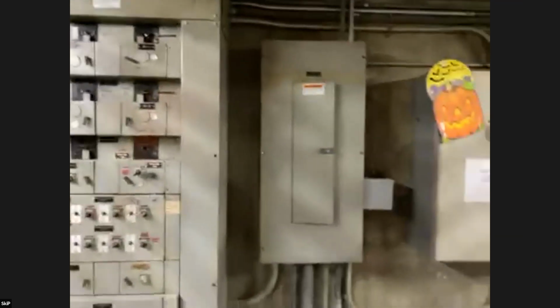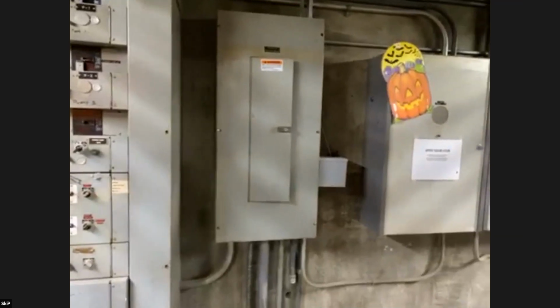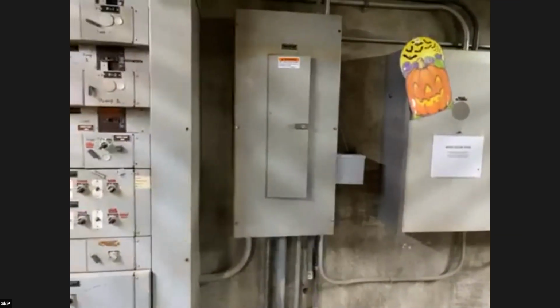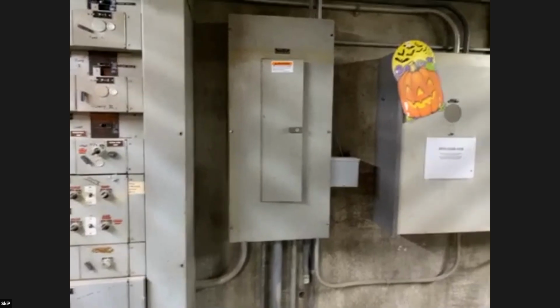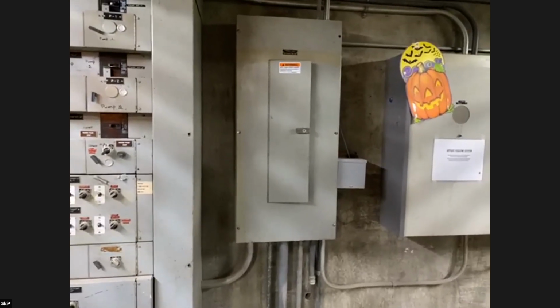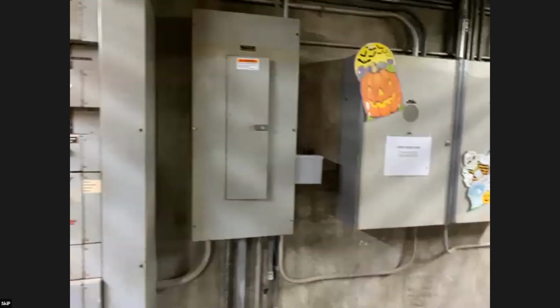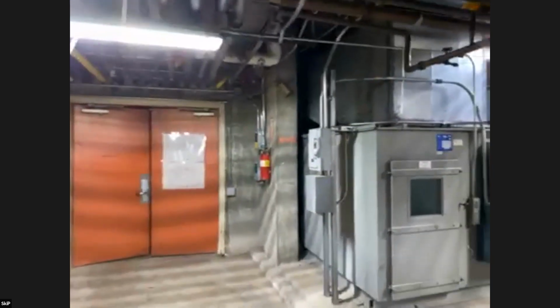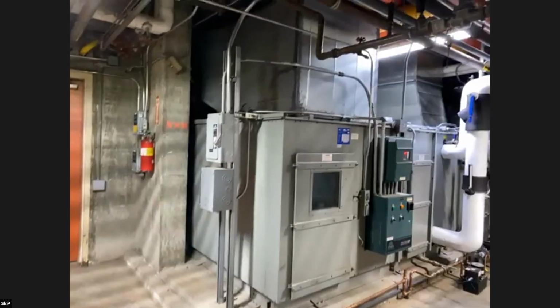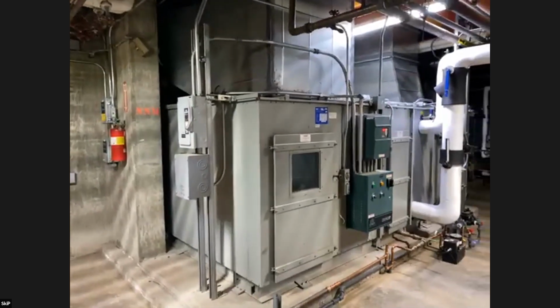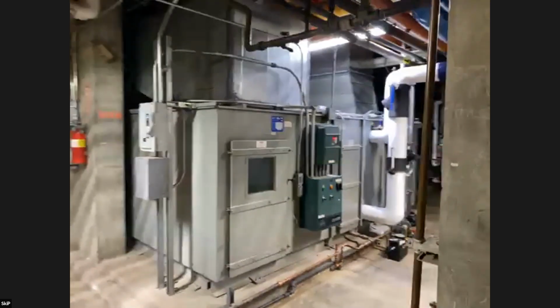The batteries were not really designed for solar, they were designed for peak demand. Our energy bill's peak demand charge is based on the worst 15 minutes of the entire month. So let's say we did 25 days really, really good, and then on day 26 we turned on every single light switch and every single chiller at the exact same instant. The amount of energy needed for that 15 minutes would be really high, so the battery kicks in to keep that number lower. Then we charge the batteries up when demand is less, like at nighttime.